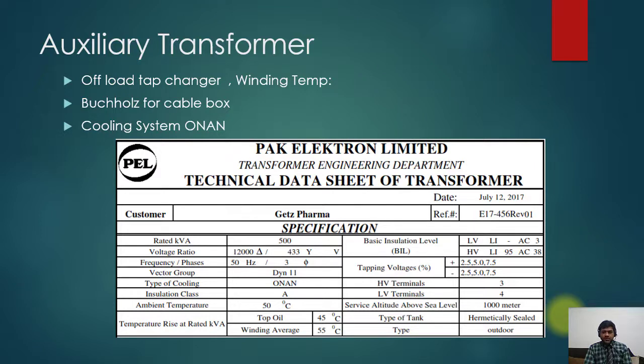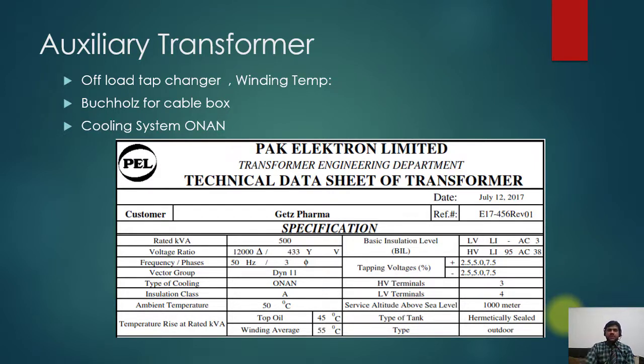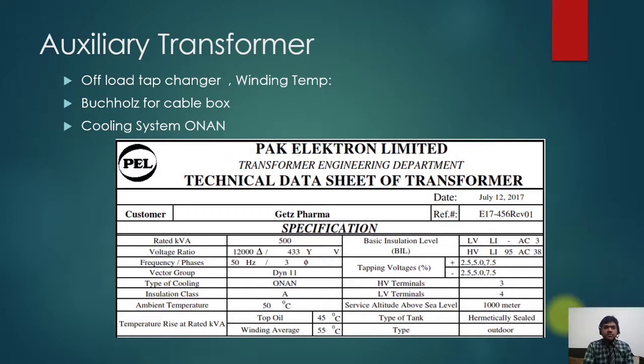One difference this transformer has is an offload tap changer. Mostly you have seen it is not on-load — you have to switch off the transformer and then manually change the taps on the top of the cover. There is one point given; you have to push it up, then you can change to the next point, and then release it back. By this way you can change the taps.